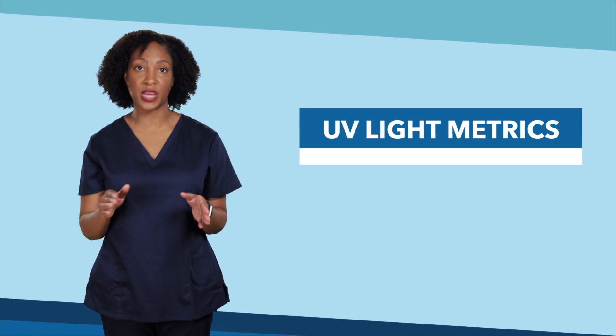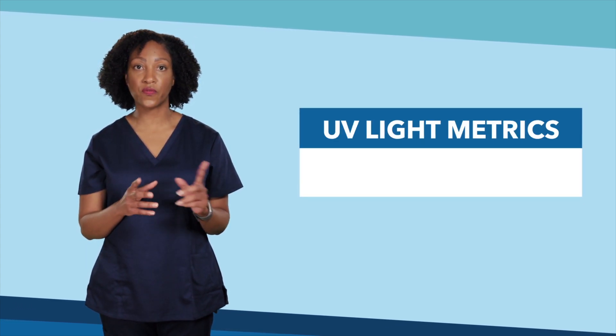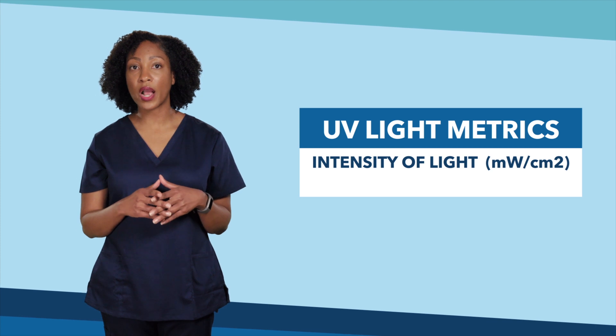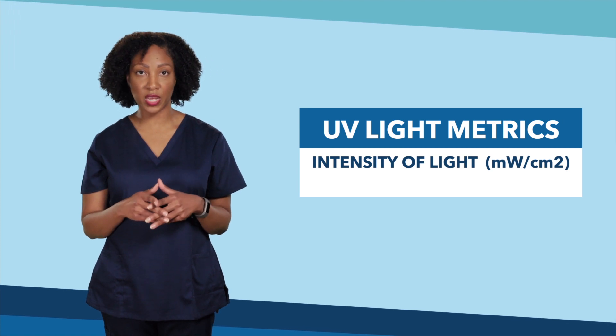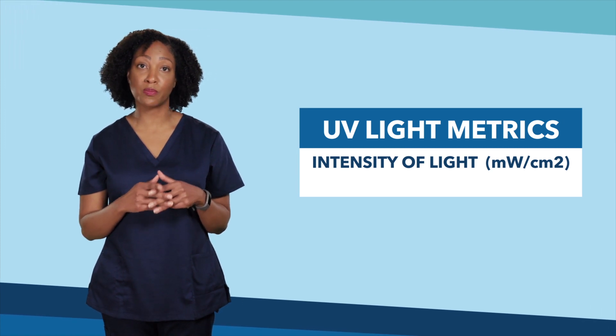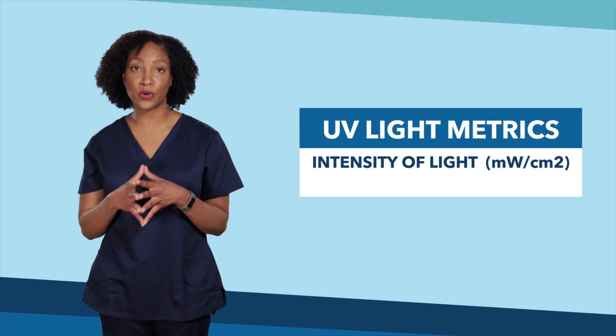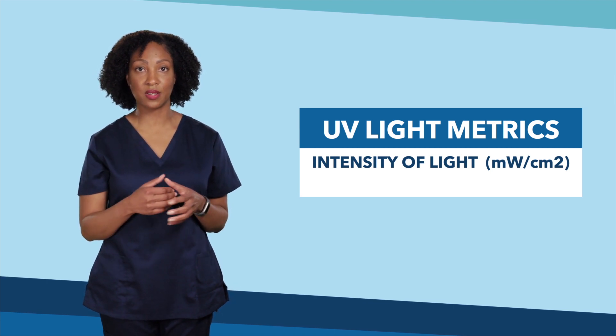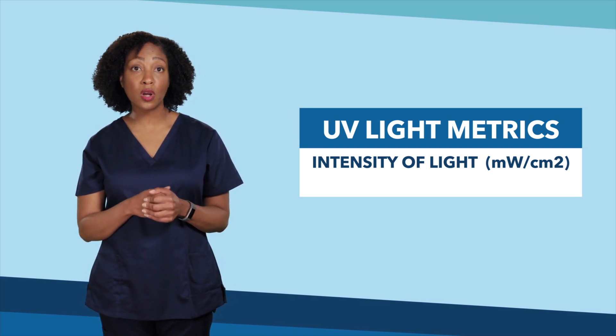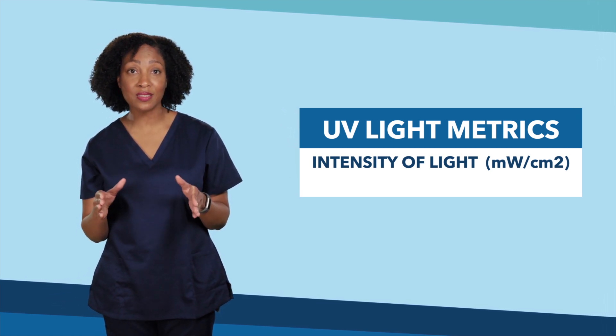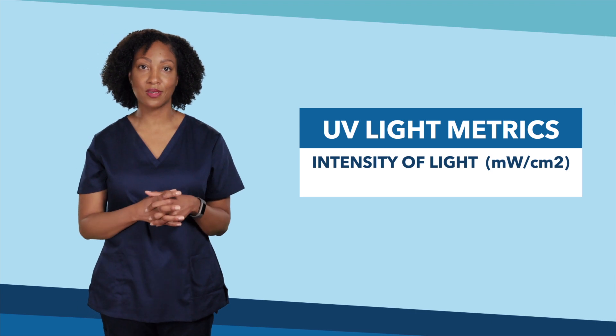Killing germs with UV light requires two important metrics. The first is the intensity of the UV light, or how much UV radiation the bulbs are producing. It's measured in milliwatts per square centimeter. The stronger or more intense the UV light, the faster it can kill germs.